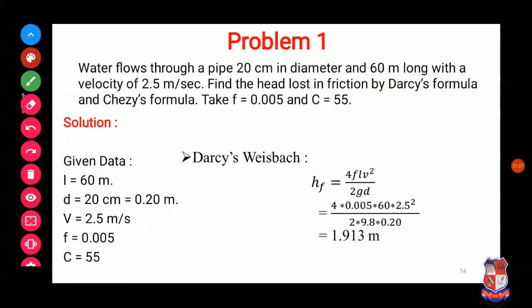Now first, find the loss of head due to friction. Firstly, find it from the Darcy-Weisbach equation. The Darcy-Weisbach equation is HF is equal to 4FLV square by 2 into G into D. Now 4 into F value 0.005 into 60, the length of pipe, into velocity 2.5 square, divided by 2 into G, that is 9.8, into diameter in meter 0.20. Now we solve it and we get the answer 1.913 meter.